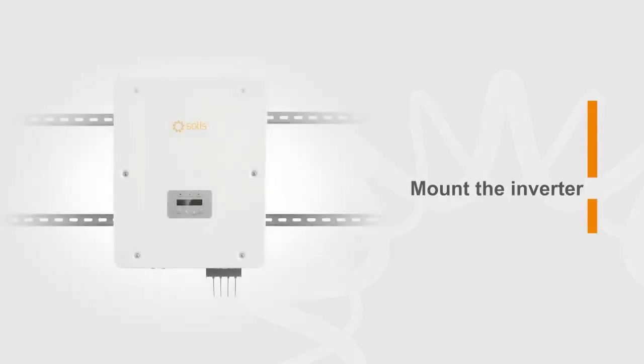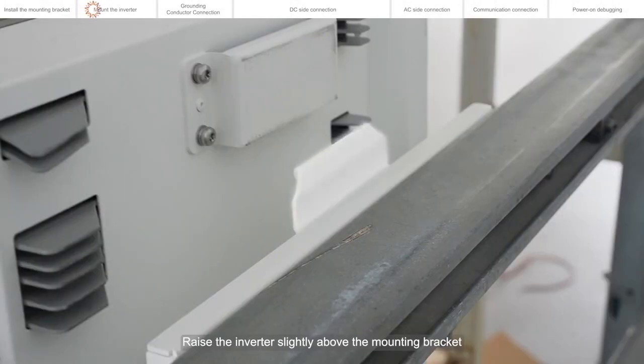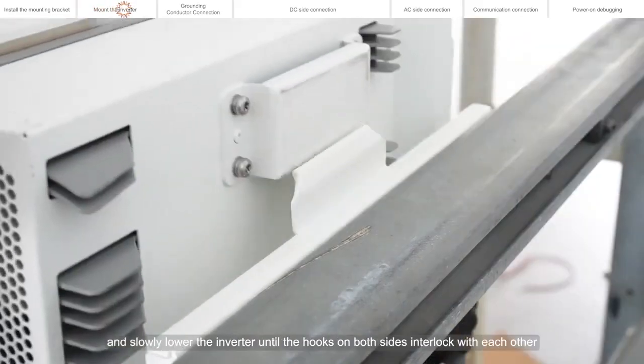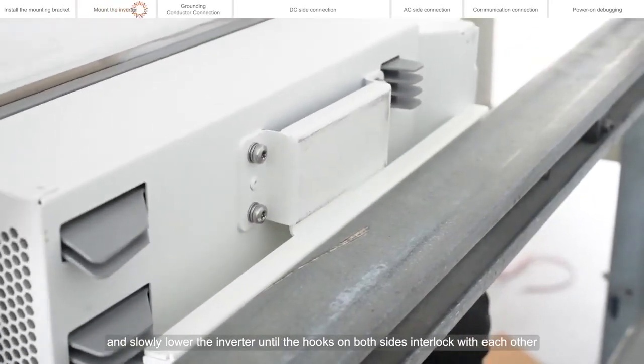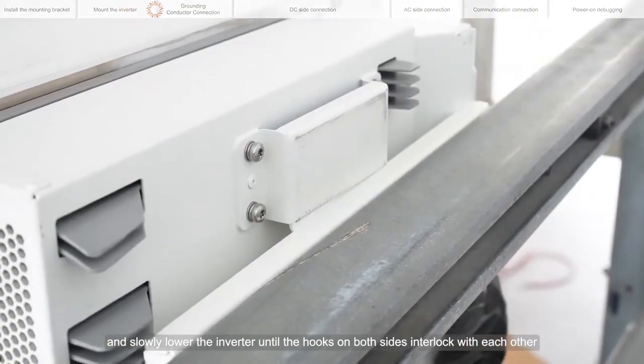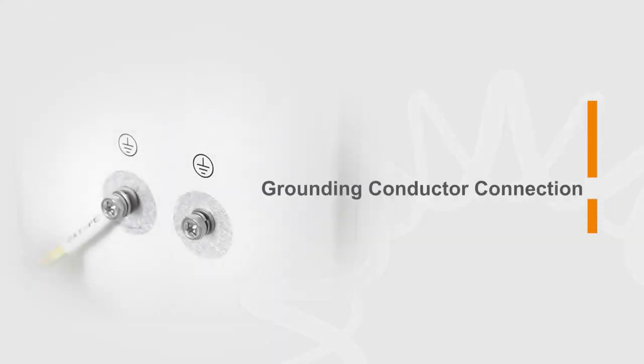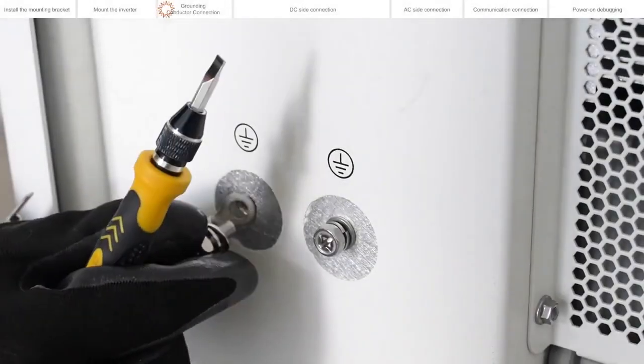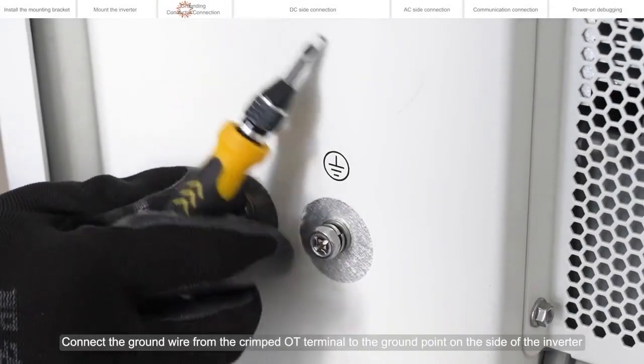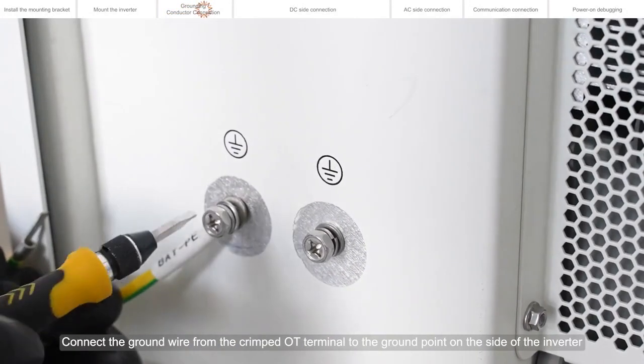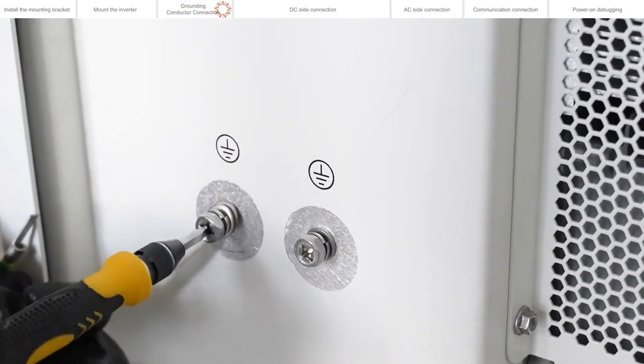Mount the inverter. Raise the inverter slightly above the mounting bracket. Align the inverter hooks with the hooks on the mounting plate and slowly lower the inverter until the hooks on both sides interlock with each other. Grounding conductor connection. Connect the ground wire from the crimped OT terminal to the ground point on the side of the inverter.